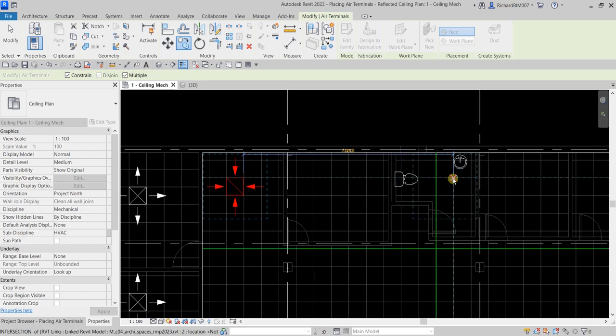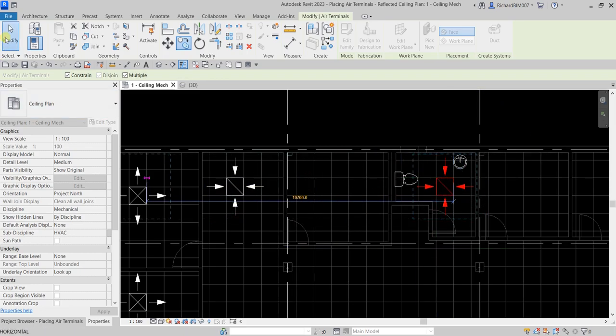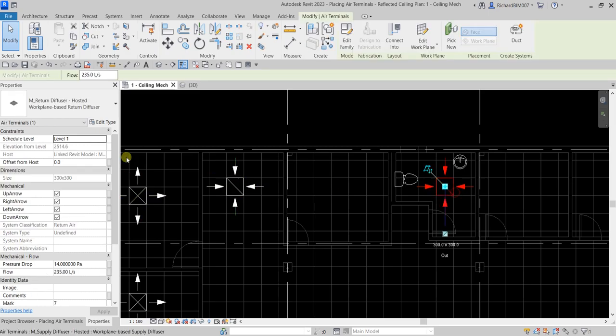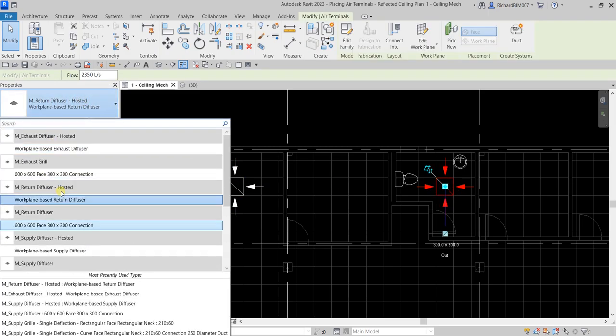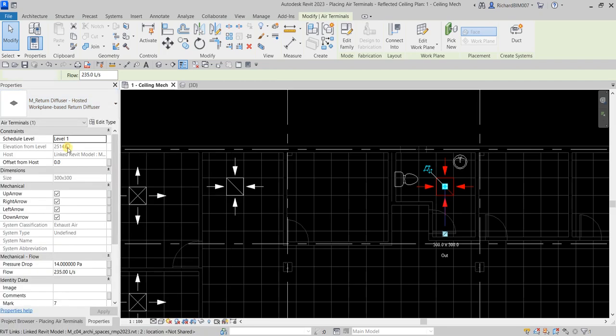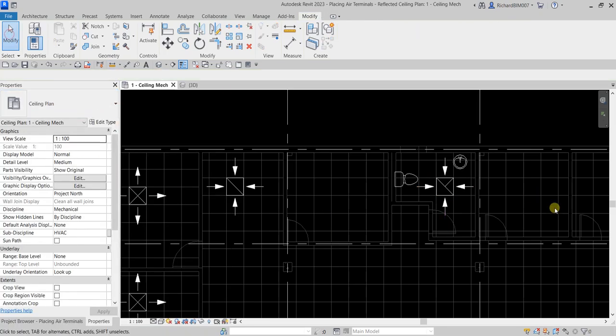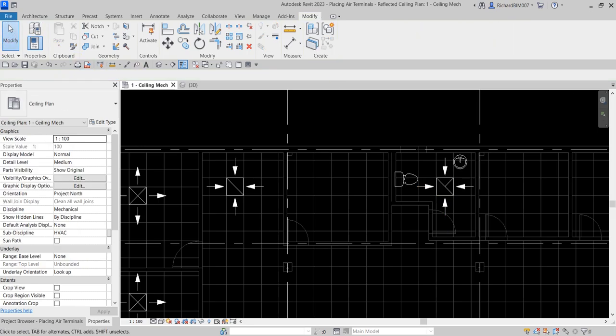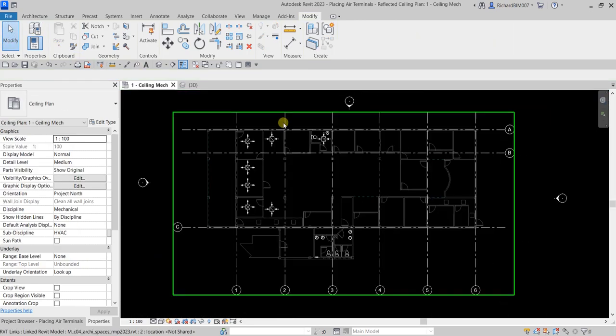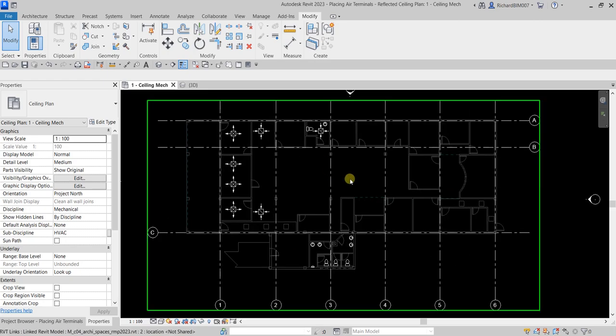Copy an air terminal to the exhaust location, select it, and change the type to Exhaust Diffuser. Then change the flow rate — I'll set it to 120 liters per second — and click Modify.